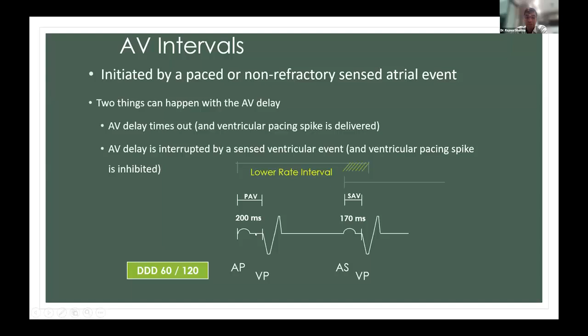So what is the paced AV delay? It is the time period between the paced atrial event and the next paced ventricular event. The pacemaker spike initiates the paced AV delay timing cycle, and it can be programmed. Regarding sensed AV delay, it is the time period between the sensed atrial event and the next paced ventricular event. The pacemaker has to sense the atrial event first, because the pacemaker electrode has to sense the atrial signal and then start the AV delay.